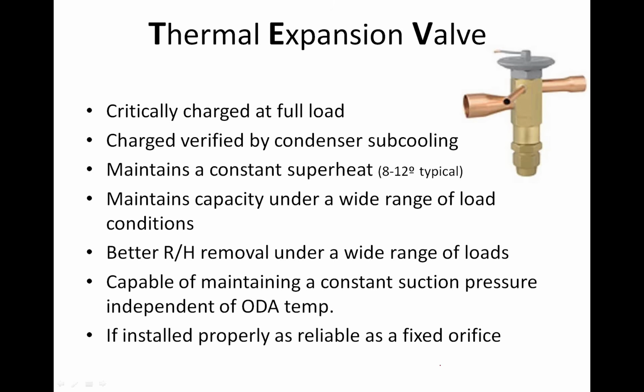Now, a TXV will operate within a range of superheats. When I say 8 to 12, typically it'll maintain within 1 degree. So the valve could be set at 8, 10, 12, 11, who knows what it's set at. We have to measure that to see what it's set at. But the manufacturer statically sets the valve. In other words, they set it by spring pressure at the factory, and it's set at what it's set at. So when we check superheat on a TXV, it should fall within 8 to 12 degrees, but it's going to try and maintain what its setting is.